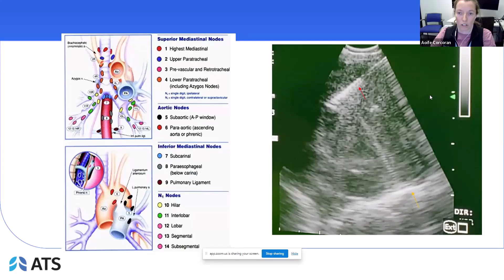When we talk about radial EBUS, it's a radial probe. This is different. This is not a scope. This is a probe that's inserted through the working channel of another bronchoscope, so you need a channel that's big enough. It can be 1.7 millimeters if you're just using the probe alone. If you're going to use the guide sheath, which is really just a plastic sheath that the probe can then go through, you do need a channel that accommodates 2 millimeters.